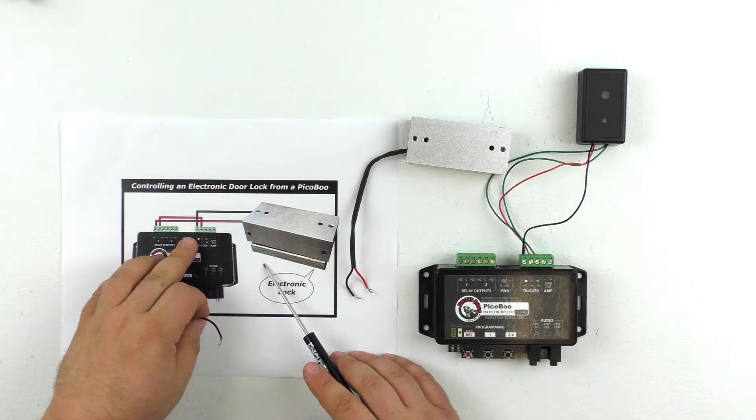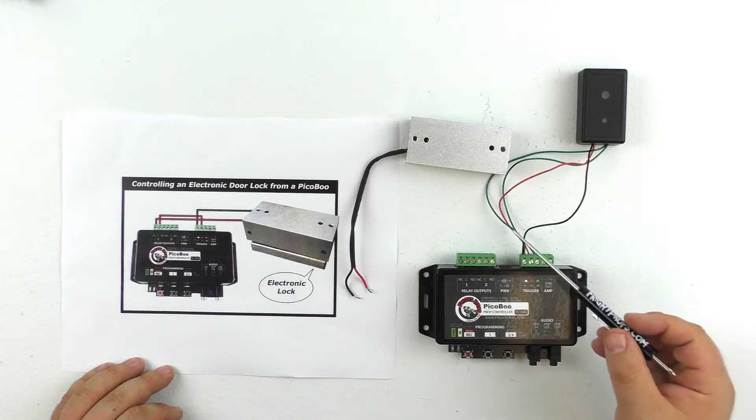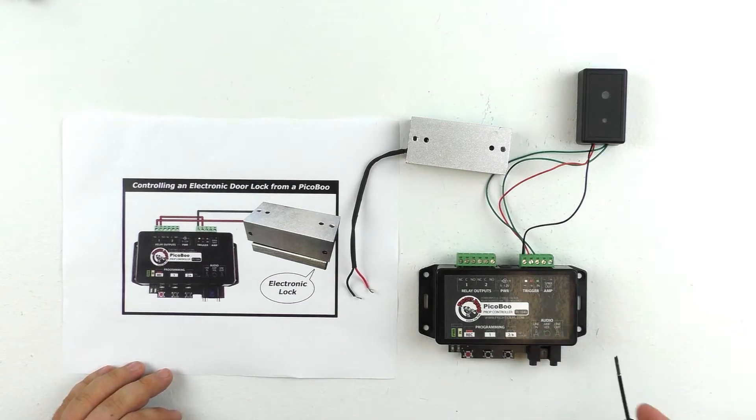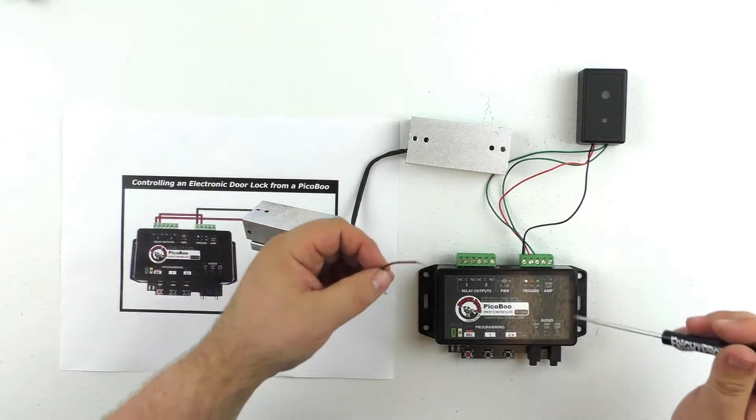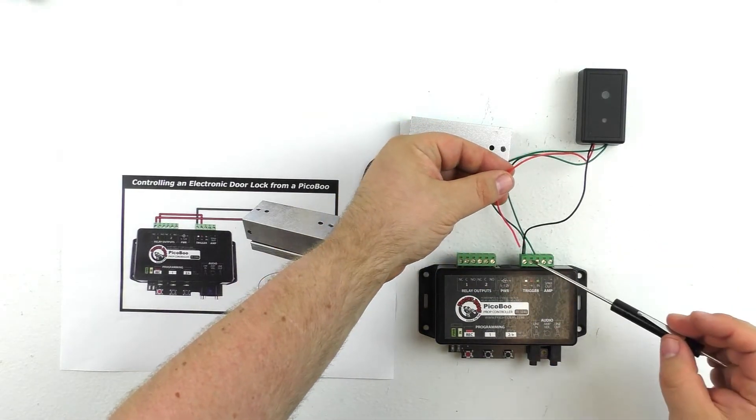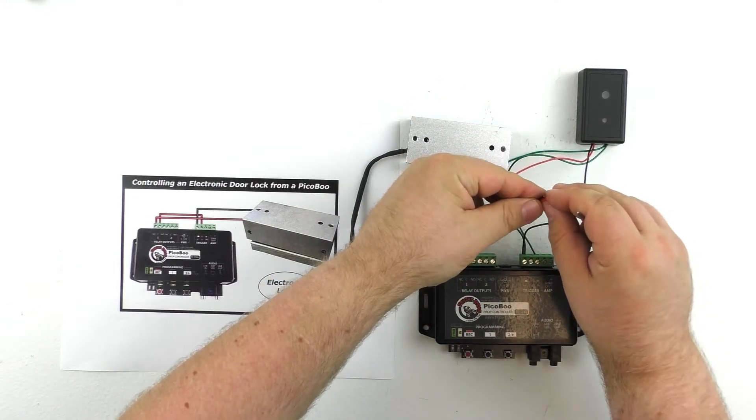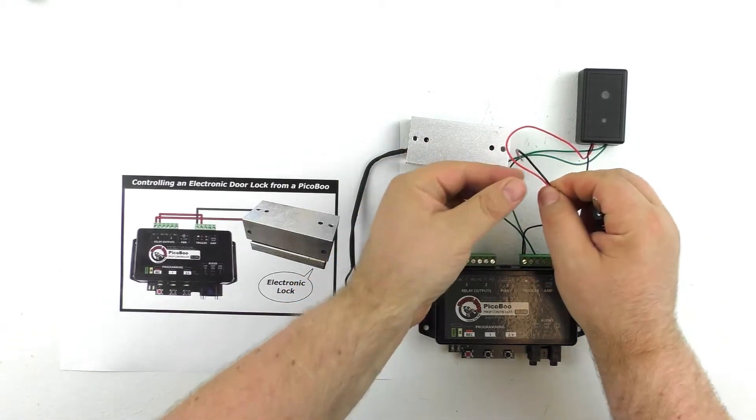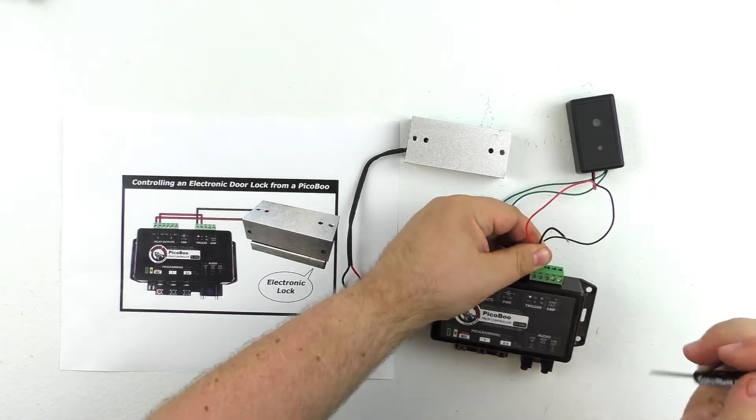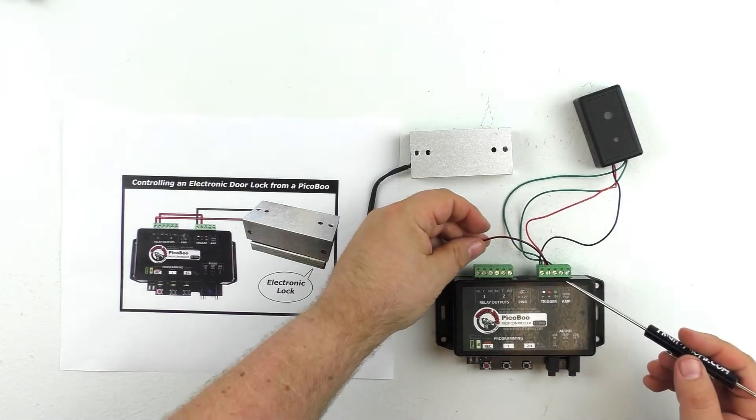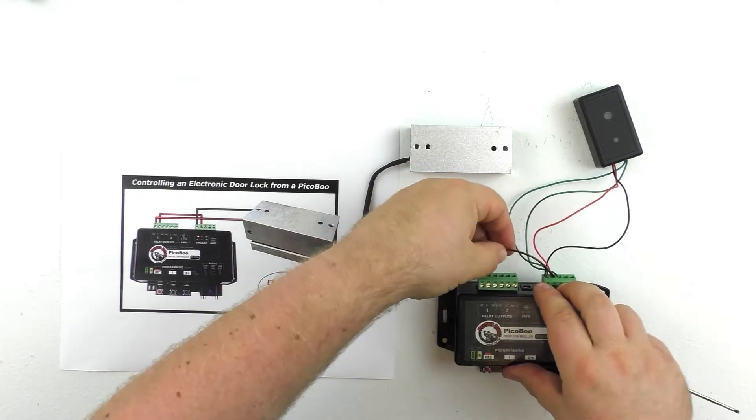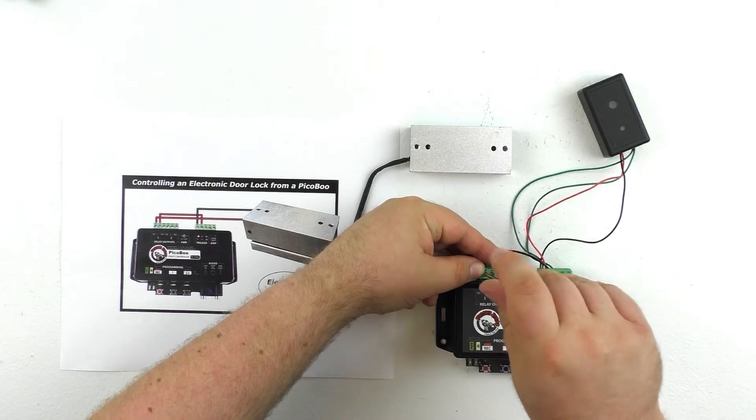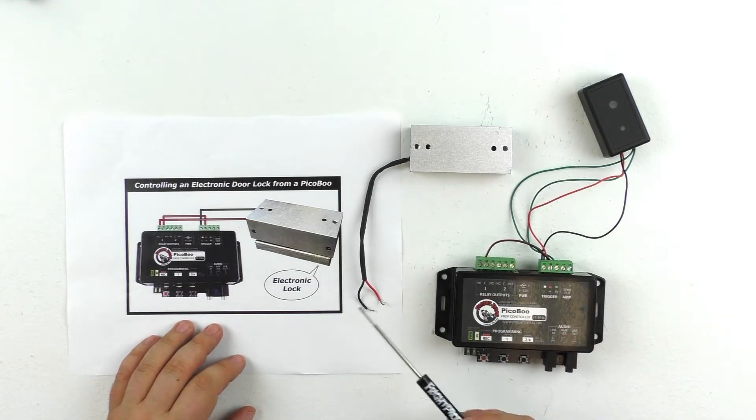I usually like to start wiring with the jumper wire. So you can see here we have a jumper wire in the diagram going from the trigger positive over to the common terminal of the relay output that we're going to be using, which is relay one in this case. So I have a small length of 22 gauge low voltage wire here, and we're just going to go ahead and wire that into place. You'll notice that we already had the wire from the sensor going into that terminal. That's okay. The two wires can share the same terminal. We're just going to go ahead and twist them together and reinsert back into the terminal. So the jumper wire is in the positive of the trigger. We're just going to bring it over into the common terminal of our relay output number one.